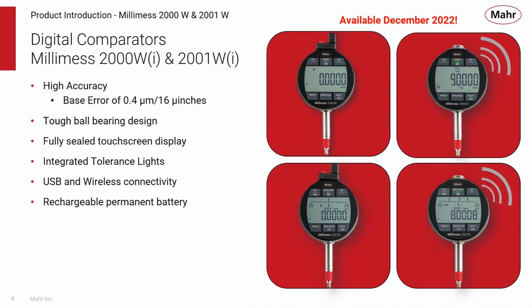Available this December 2022, Mahr will be introducing to the market two new indicators, digital comparators, the Millimess 2000 and 2001. Features and highlights: it's going to be a very highly accurate gauge, with a base error of 0.4 microns. The internal movement itself is a very tough, long-lasting ball bearing design, designed to eliminate almost all lateral loads and make for a very repeatable movement of the device itself.